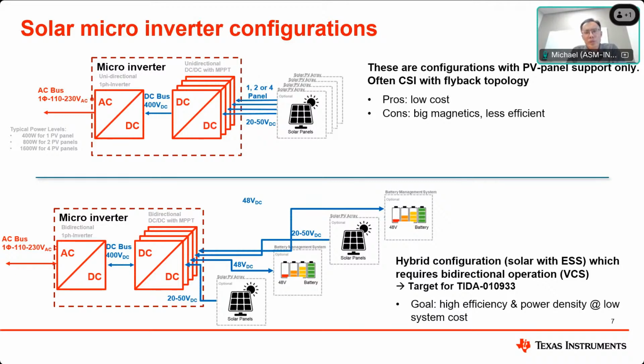There are different configurations for microinverters. You will see one microinverter supporting one PV panel, 2, 4, or even more. Those PV panels are connected to an individual DC boost stage. The power level ranges from 400 watts for a single panel to 1.6 kilowatts and even more for a quad-channel configuration.